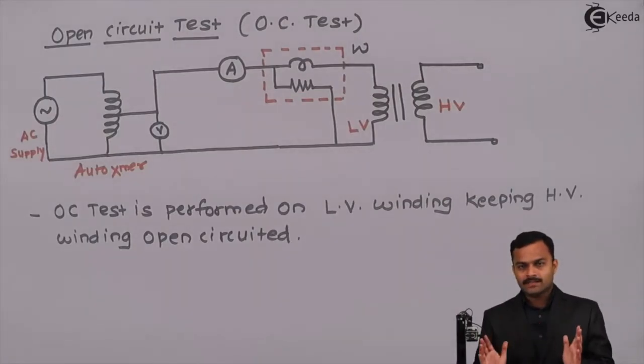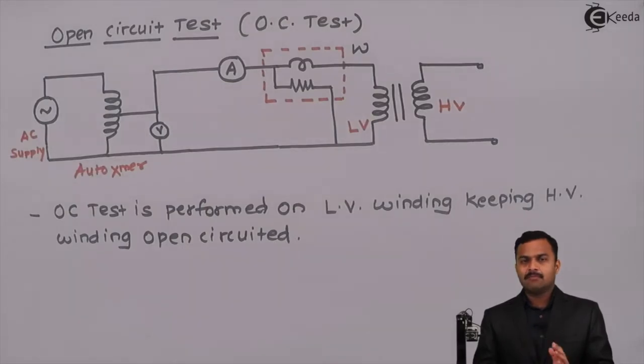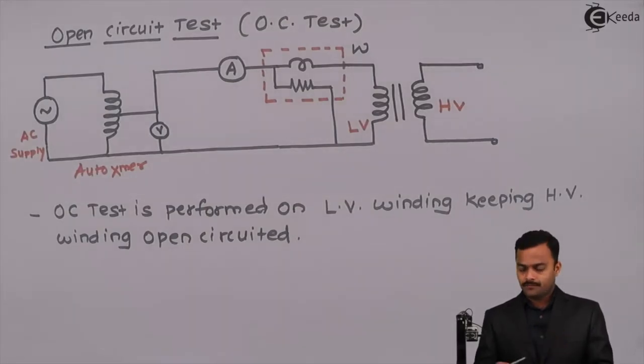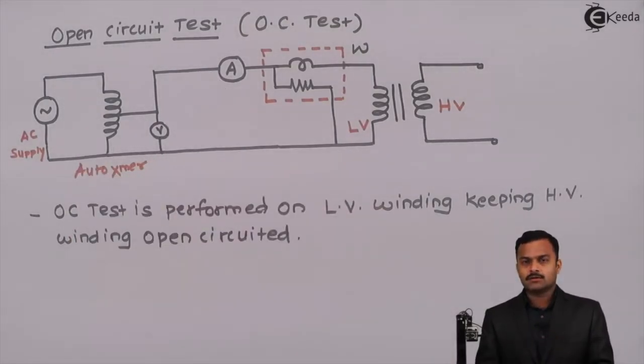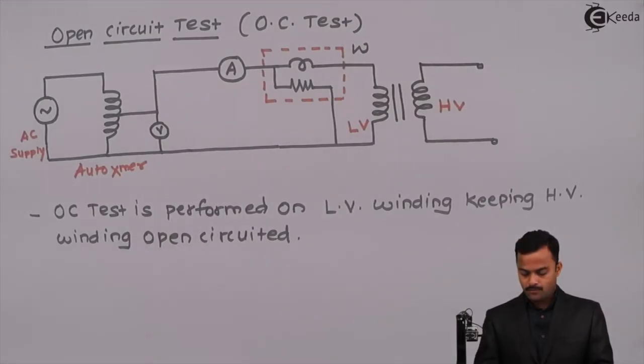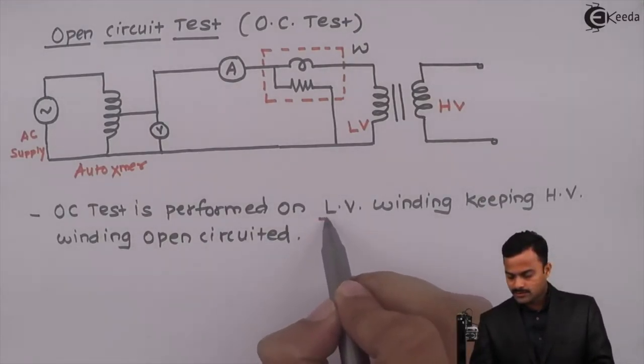Otherwise it is fine — it would give the same results. But because of the restrictions on meters, we perform the open circuit test on the low voltage winding.